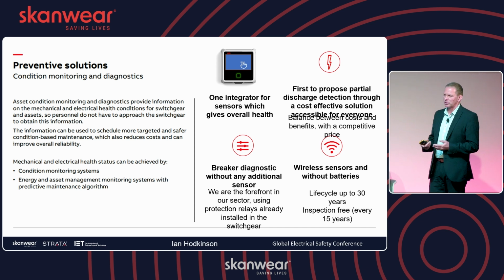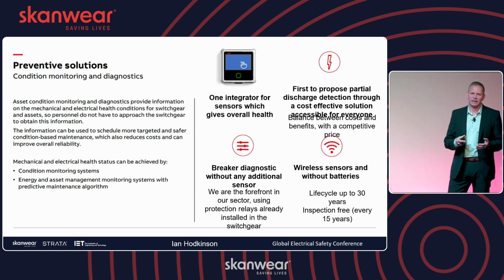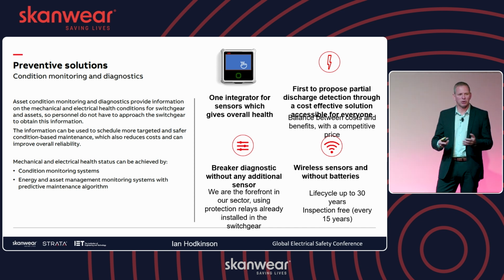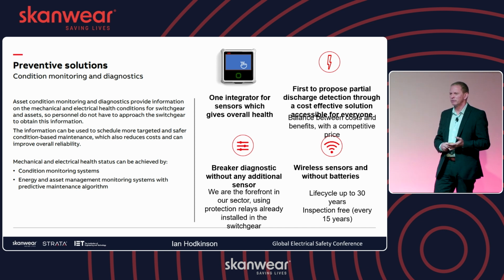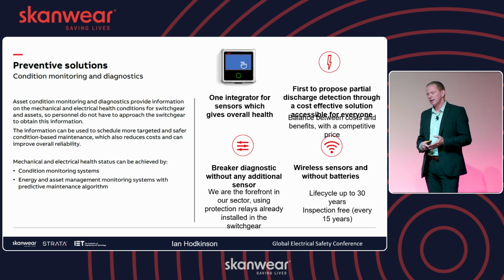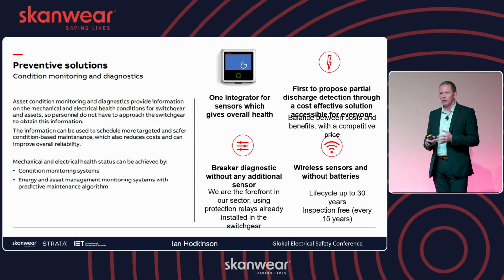This enables condition-based maintenance rather than just time-based maintenance, helping highlight any hot spots or issues with your switchboard to prevent major incidents. Combined with modern protection relays that have all the information on the breaker, such as switching, timings, and number of operations, all that data can be brought back with the sensors over comms into the SWICOM, which can then be accessed remotely.